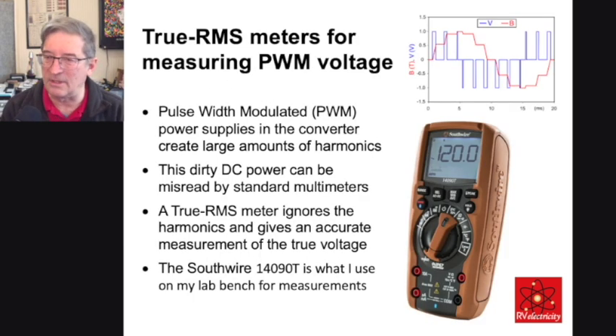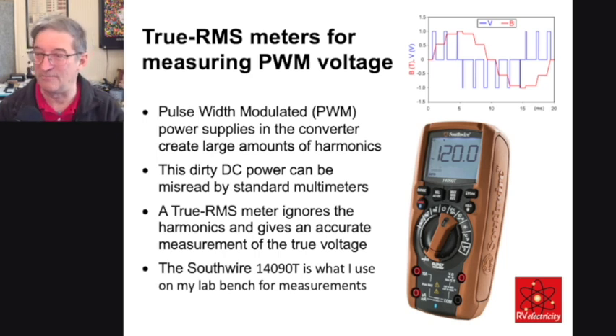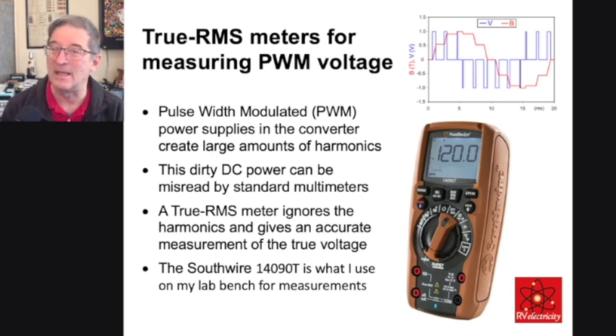It can measure 24 volts if you set it to AC while measuring a battery. So even though you can get a decent meter that will do a lot of work for you, costing $15-20, true RMS meters are really better for professionals because you encounter a lot of things that are not exactly pure voltage.